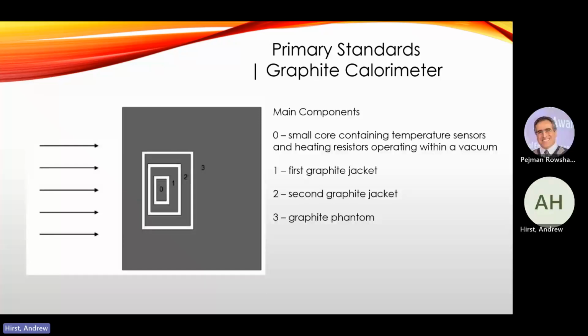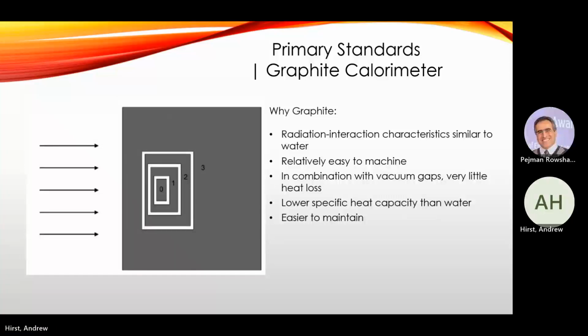So you have a core, which is within a graphite jacket and a vacuum seal, a second graphite jacket, and then the whole phantom is graphite. So why graphite? It has radiation interaction characteristics somewhat similar to water. It's quite easy to machine, so you can create the calorimeter with relative ease. Using those vacuums, there's very little heat loss compared to something like water. It has a lower specific heat capacity than water, so you can heat it up quicker with the same amount of dose, so it's a bit more sensitive, and it's easy to maintain.